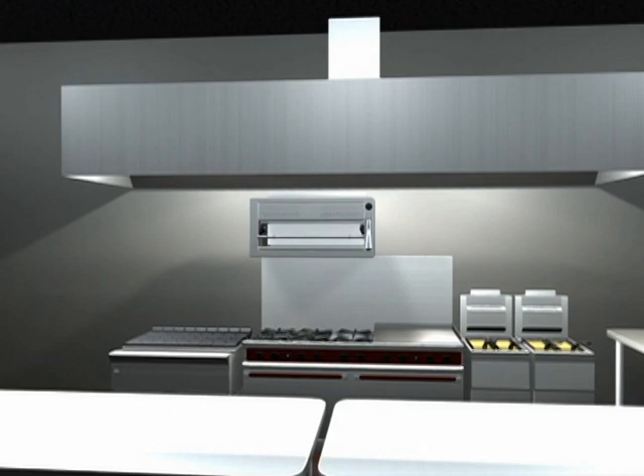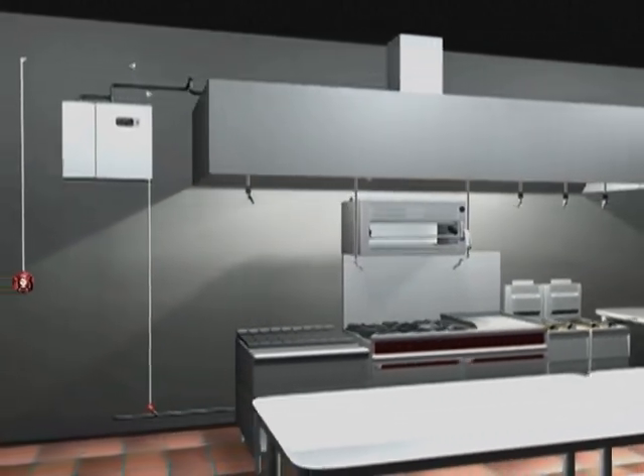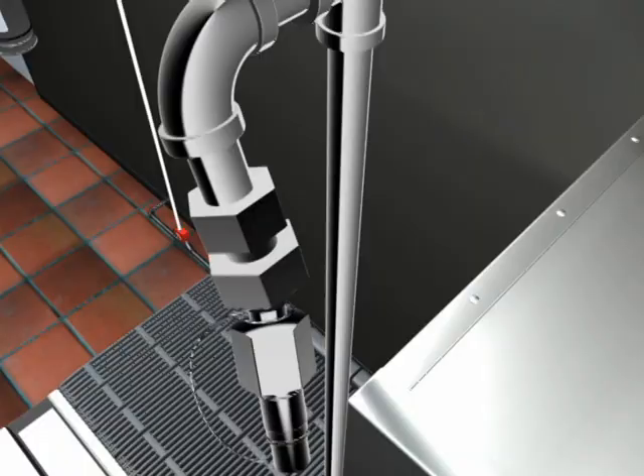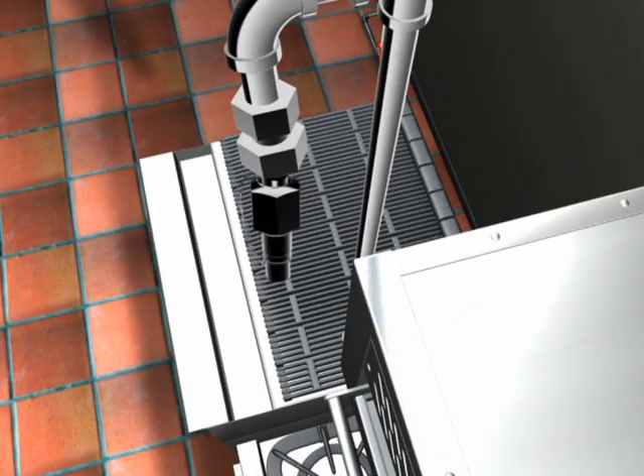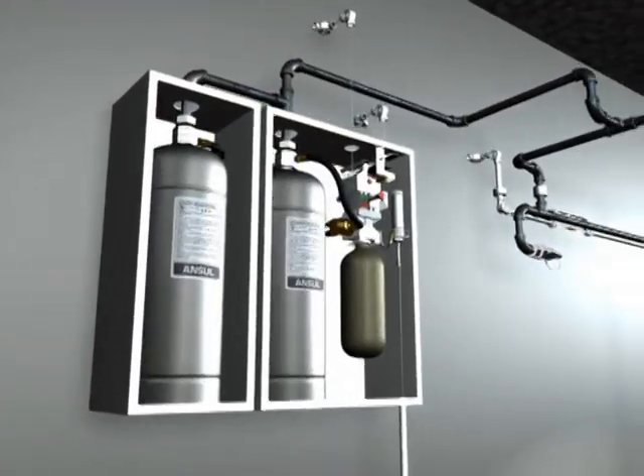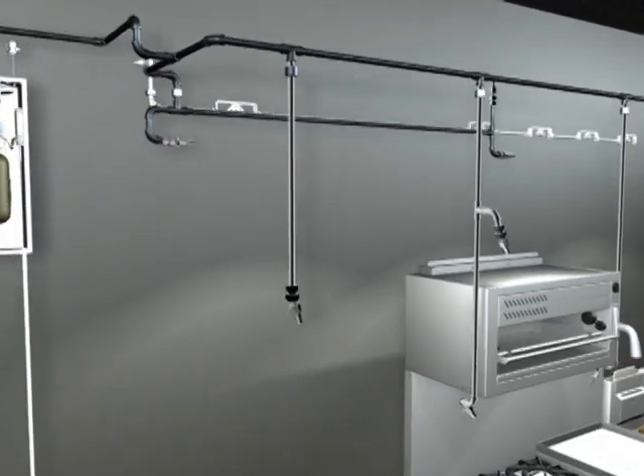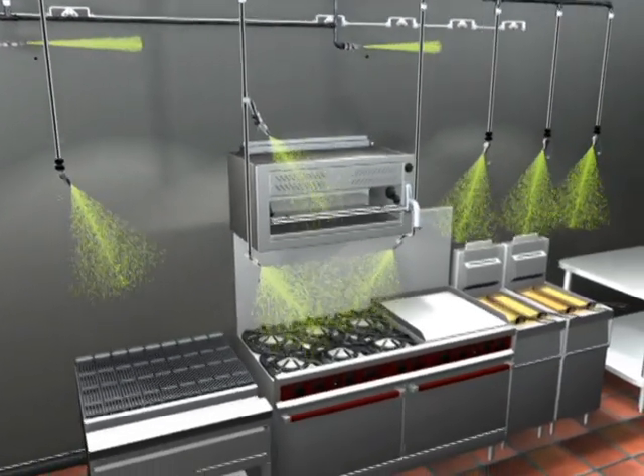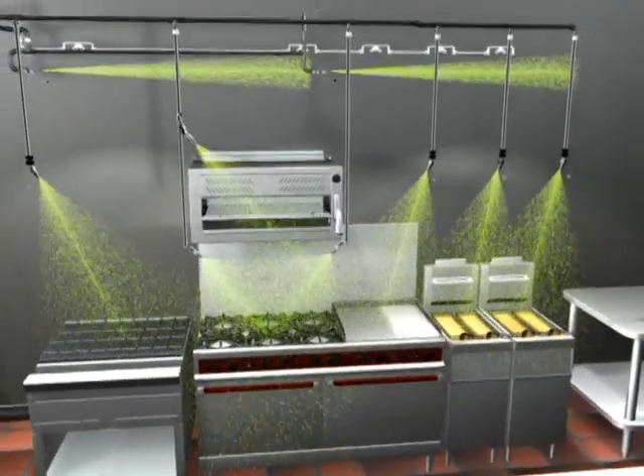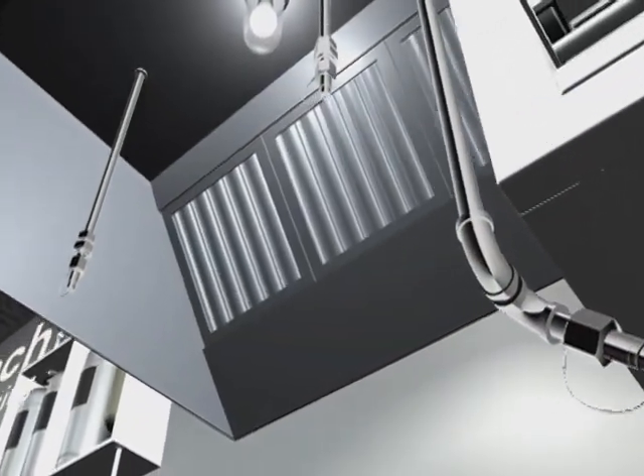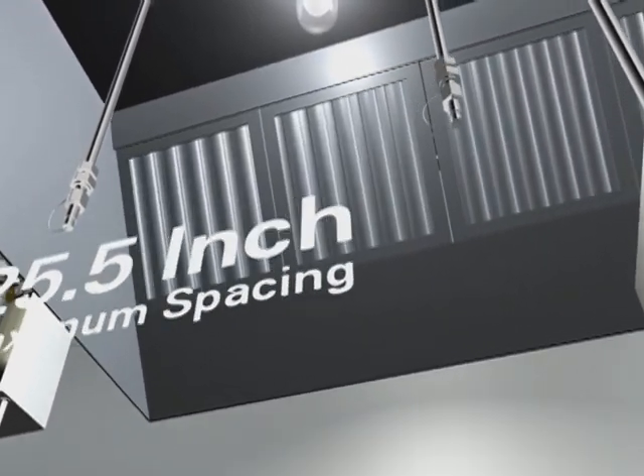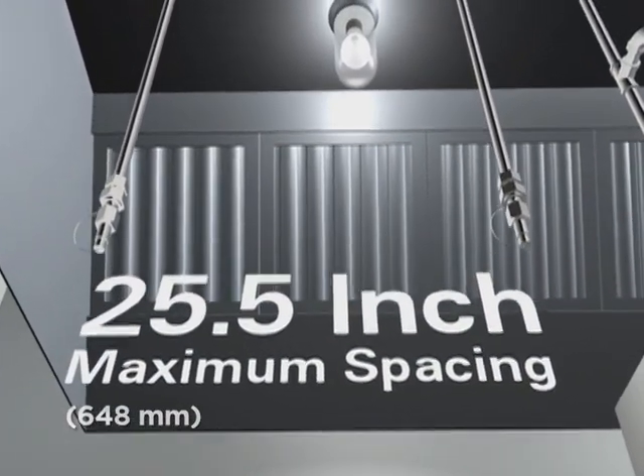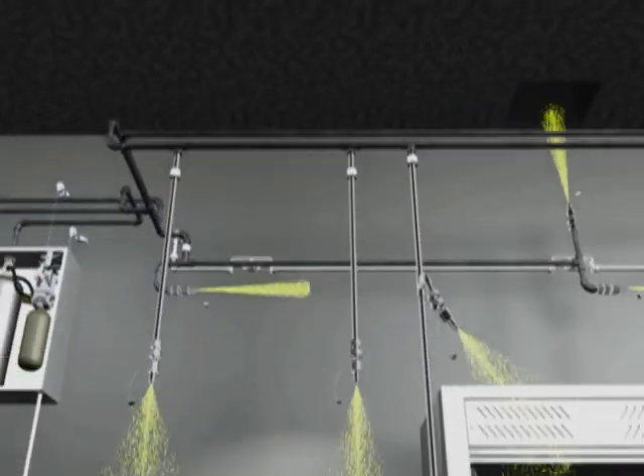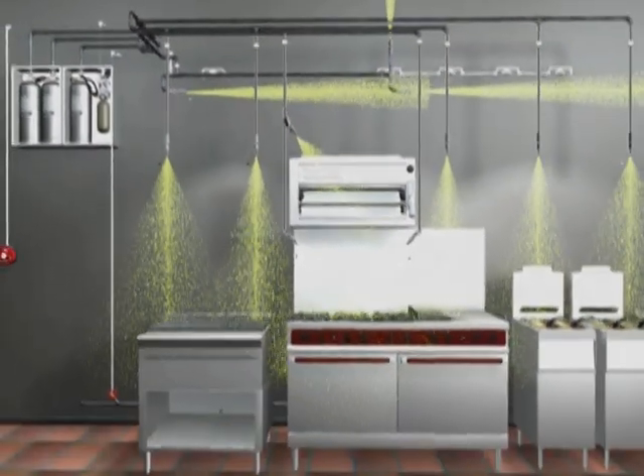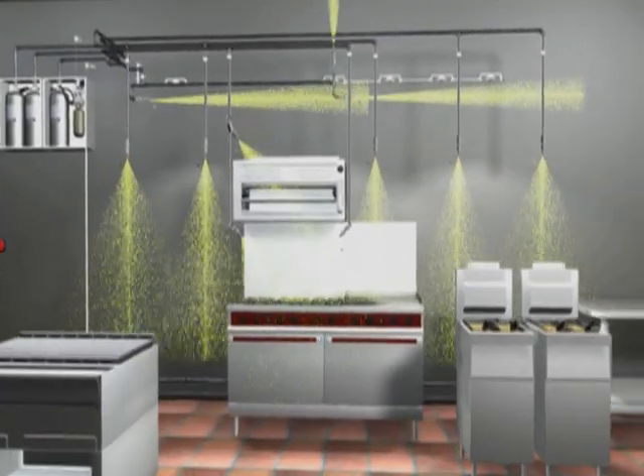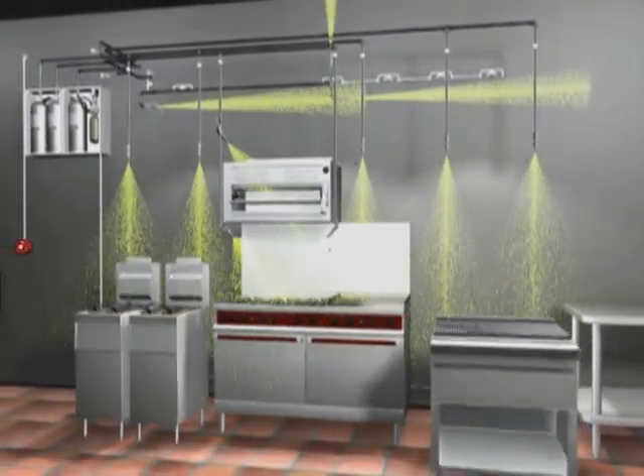With R-102, there are two system design options. The primary is an appliance-specific design where nozzles are aimed at specific hazard areas of the appliance. This is considered the most economical design because the agent is aimed only where it is needed. The other option is overlapping appliance protection. In this design scheme, the nozzles are installed in a straight line and provide overlapping discharge patterns. Using this layout, appliances can be moved or replaced, and as long as they stay within the fire-free zone, they will be protected.